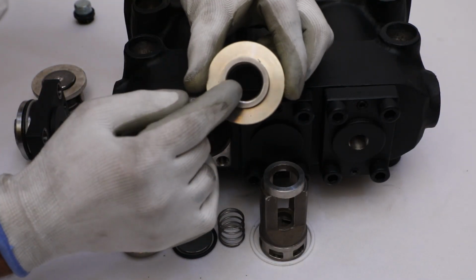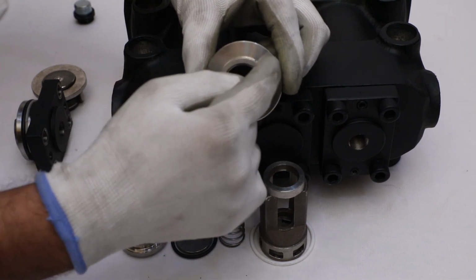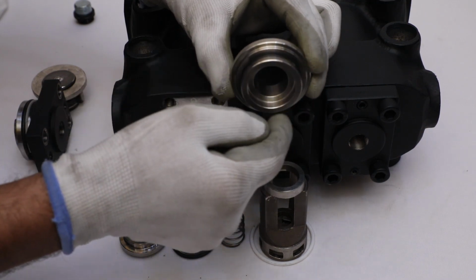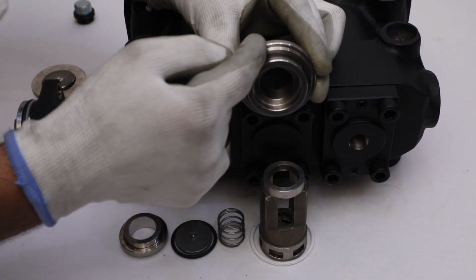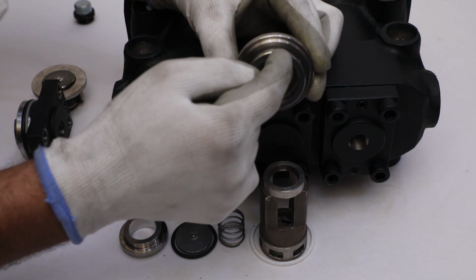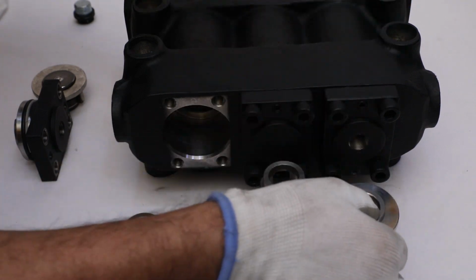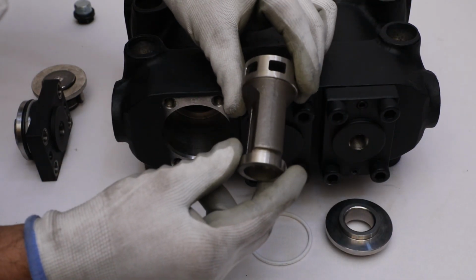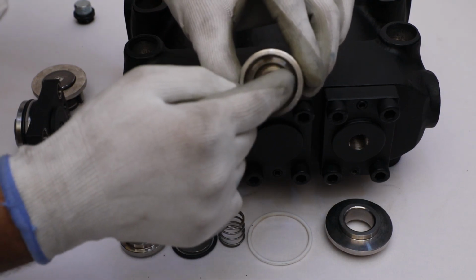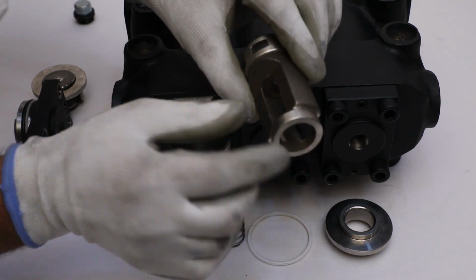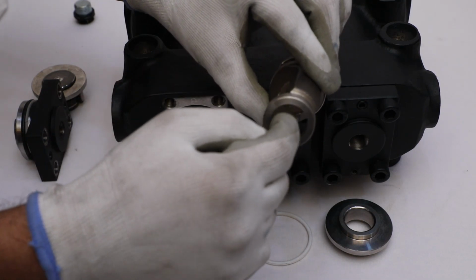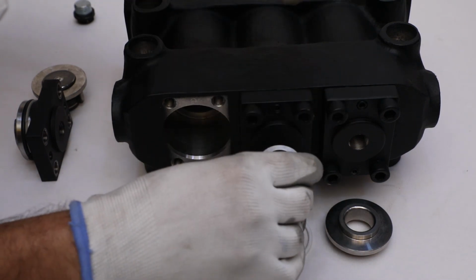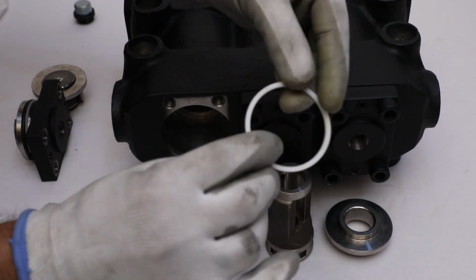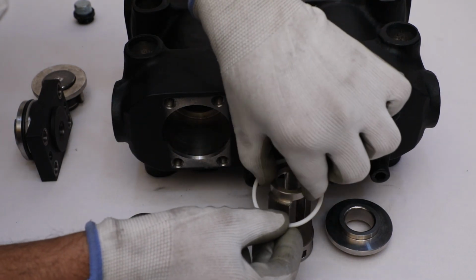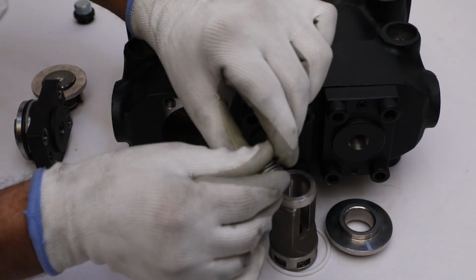Inspection of valve assembly. Check upper, inner and flat surface. Also, look into the opposite step surface of discharge valve seat for any wear or dent marks. Inspect suction valve seat guide's inner step surface, periphery and a top surface for any damage. Check PTFE gasket for stiffness and thickness. Check stiffness of helical spring.